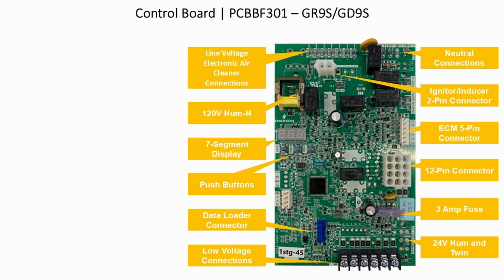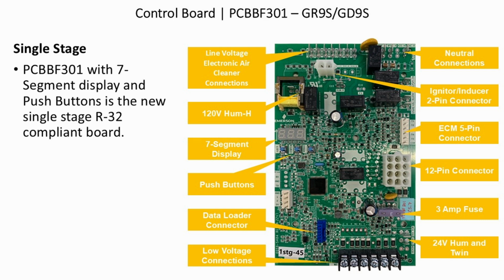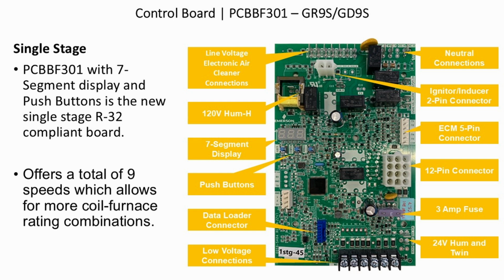Control board, the PCBB F301 on the GR9S, GD9S furnaces. Single stage, PCBB F301 with 7-segment display and push buttons is the new single-stage R32 compliant board. Offers a total of 9 speeds which allows for more coil furnace rating combinations.